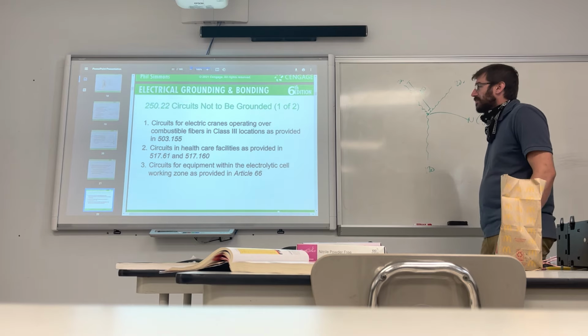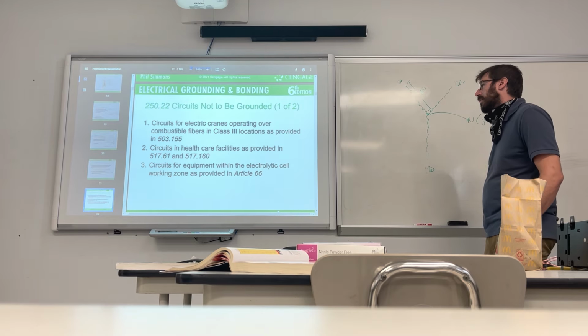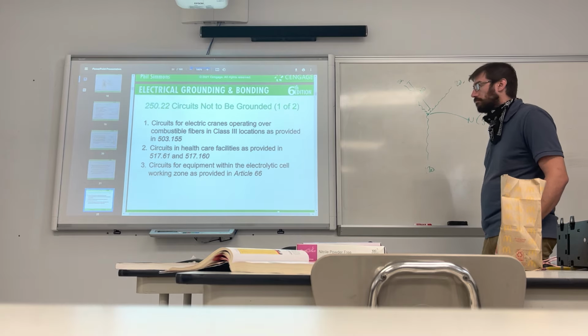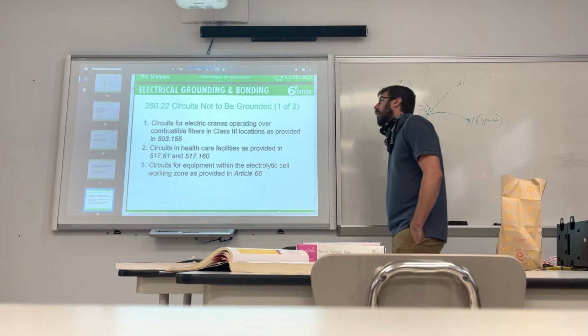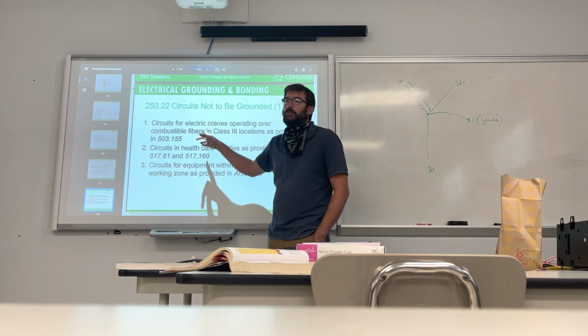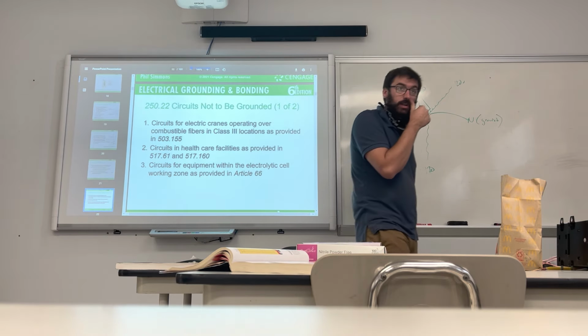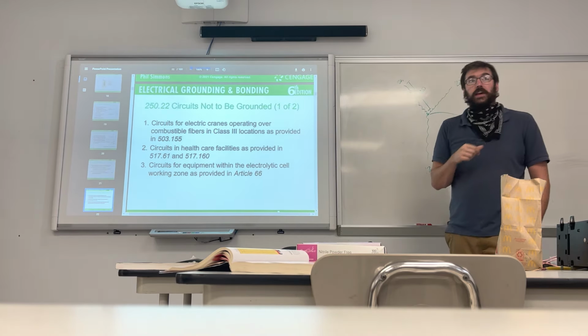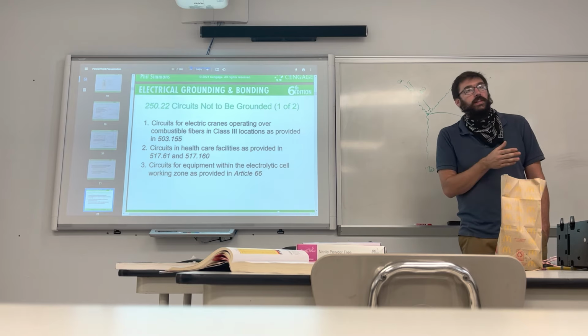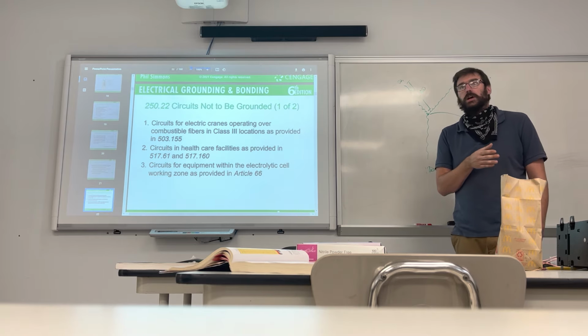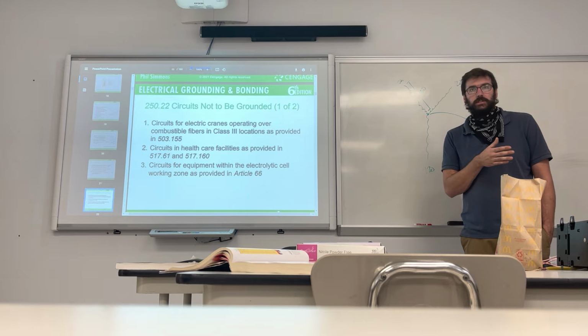Circuits in health care facilities as provided in 517. Circuits for equipment within the electrolytic cell working zone as provided in Article 668. All right, so those are things not to be grounded. I made sense of that one before with the crane, right? If that's a combustible fiber line and that crane touches a high voltage line and that line explodes, that can hurt a lot of people on the ground. So that's why the crane is ungrounded.